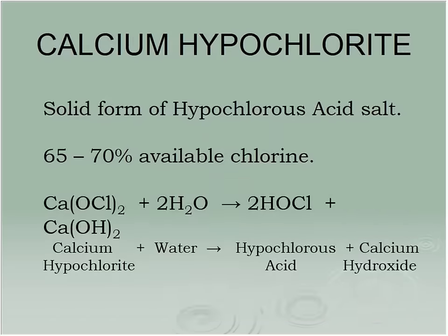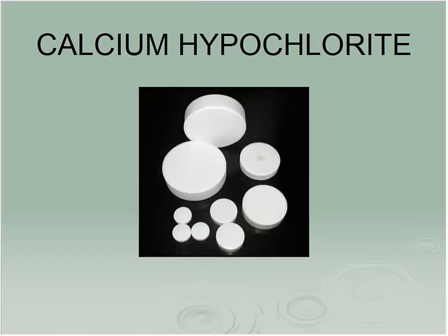Now, there are some very small systems, might be an alternative system, or it might be a lagoon system, that will use calcium hypochlorite. If you've ever had a pool and used HTH, that's what we're talking about. 70% chlorine in these tablets. Got to be very careful on how you store them. But again, once you add it to the water, hypochlorous acid, same deal. You've got these tablets inside of some unit, and then you just regulate how fast the water goes through and dissolves the tablets. That's very common with lagoon systems where you don't have somebody hanging around all day long.